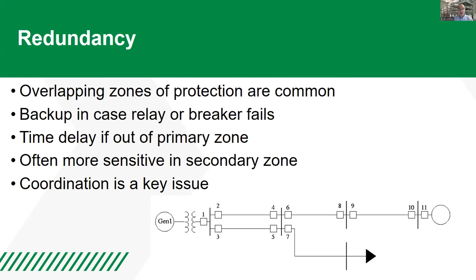For an important generator station or transmission line, there are multiple sets of measurements and multiple different relays using separate measurements and separate communication systems to the circuit breaker, to ensure there's no single point of failure preventing fault interruption. Some schemes use current measurements and respond if current exceeds a threshold, sometimes coordinating with fuses, which you see extensively in distribution systems. They also calculate effective impedance looking into a line, or do differential protection by summing the currents into a zone. Differential protection is very effective; it has some weaknesses, but relay vendors have designed solutions to work around most of those.